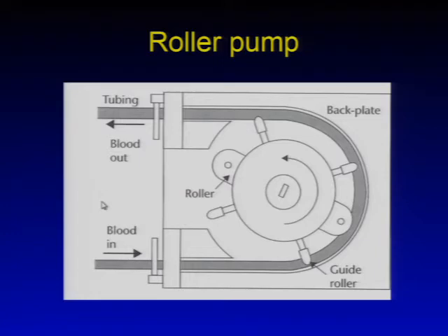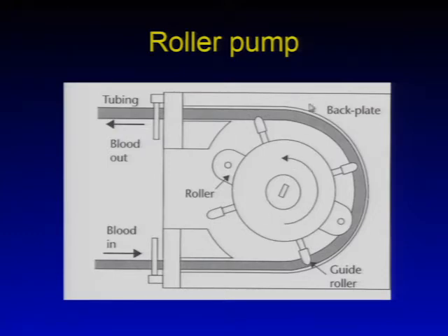The roller pump has an inlet, outlet, tubing, and a rotating roller against a back plate. When the roller rotates, it pushes the tubing against the back plate, which is the main driving force for propelling blood to the outlet. Centrifugal pumps are also commonly used nowadays and come in two types: cone type and vane type.